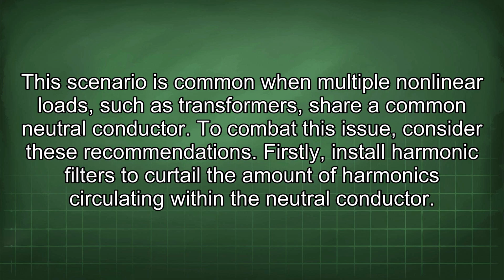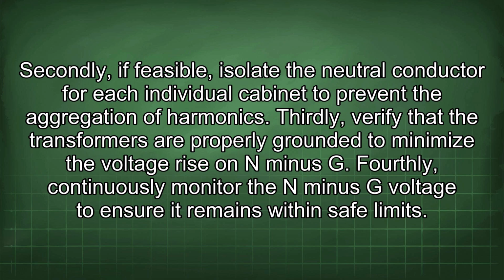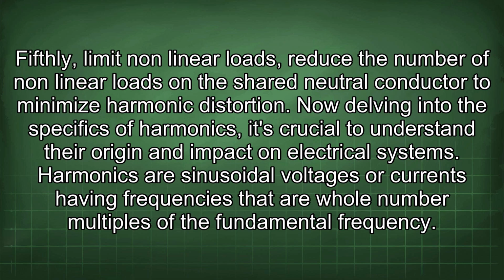Firstly, install harmonic filters to curtail the amount of harmonic current circulating within the neutral conductor. Secondly, if feasible, isolate the neutral conductor for each individual cabinet to prevent the aggregation of harmonics. Thirdly, verify that the transformers are properly grounded to minimize the voltage rise on N-G. Fourthly, continuously monitor the N-G voltage to ensure it remains within safe limits. Fifthly, limit nonlinear loads. Reduce the number of nonlinear loads on the shared neutral conductor to minimize harmonic distortion.